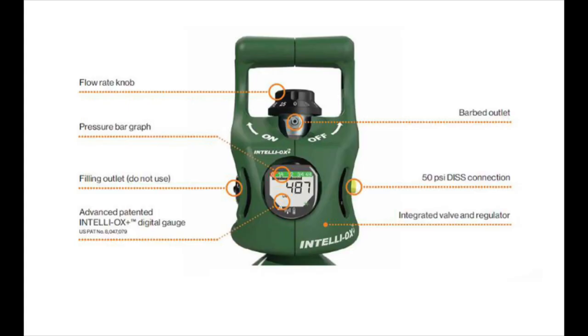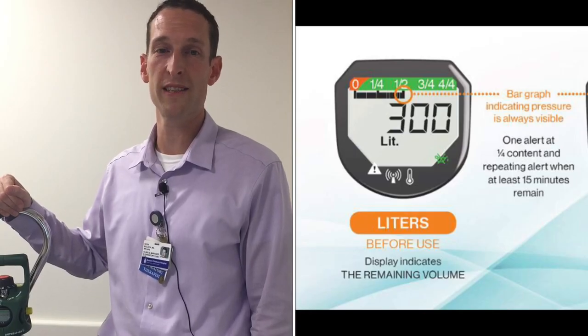The IntelliOx oxygen cylinders also contain a 50 psi DISS connection for use during ventilator transport. The most notable difference in the new cylinders and the key driver to the conversion and policy changes is that the IntelliOx system incorporates a digital display that indicates the volume of gas remaining in the tank. The display of actual volume remaining is the biggest change for us to get used to, as we are no longer looking at pounds per square inch to assess how much gas remains.